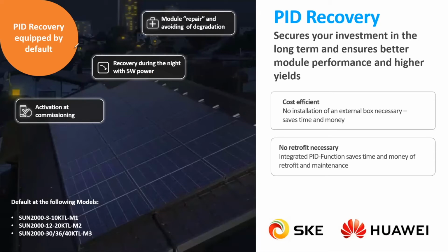This anti-PID module is included in the inverter itself, so no need for extra devices. So the three-phase residential have it, the smallest in the commercial range, 12 up to 20 kilowatts, and also the 30 up to 40 KTL, the M2 and M3 series. So this is included in the inverter. If you don't want to use it, you can disable this function. If you want to use it, it's included without any additional cost. And no retrofit is necessary in case maybe you don't want to use it in the beginning, but along the way you want to implement this function.